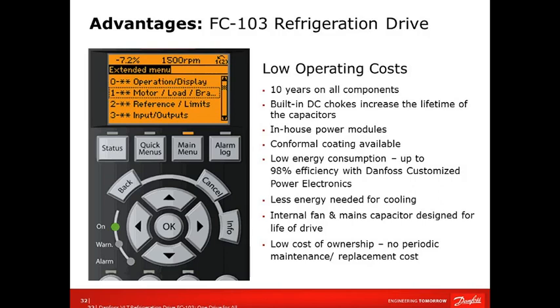When we're using the drive, everything's built for a minimum of 10 years on all the components. The DC chokes are a type of filtering that we put in the product to enhance the life of the product. You'll hear about AC line chokes and things like that. Some other manufacturers actually have to add additional filtering to meet certain specifications. Danfoss, on the other hand, builds in DC chokes. This extends the life of the internal components, and it also meets certain thresholds and requirements, and we just include it with the drive. It's more efficient than AC chokes. From our experience in doing this for over 50 years, we're trying to keep the drive alive and working as long as possible, 24/7, start up, start down, it doesn't matter, and with no maintenance, therefore low cost of ownership.